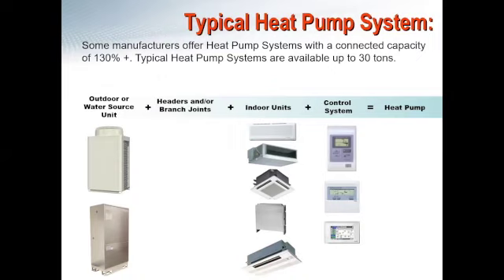I'd like to note that we touched on the air source condensing unit that we show on the top. We also have a full line of water source condensing units. While that is not usually a super widely seen application, it is something that in Japan, China, and Europe is extremely common because of how efficient it is, and they are also significantly smaller than your typical air source condensing unit. So if you have any projects that you may be working on where there is an existing water loop, or you're really, really tight on space, a lot of times a water source system can really help in servicing that application. One thing to touch on with the heat pump system and VRF in general is that you can overconnect these systems.